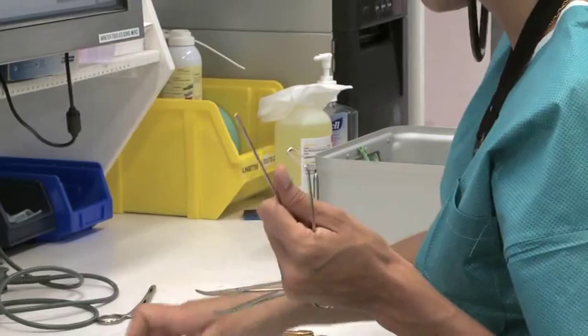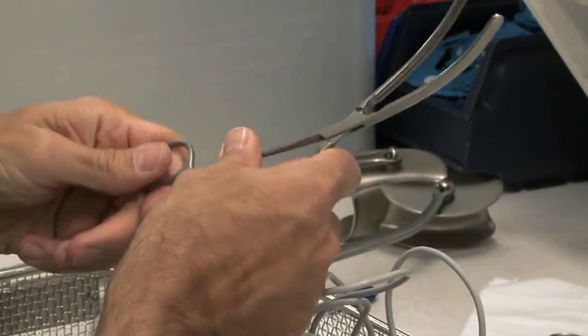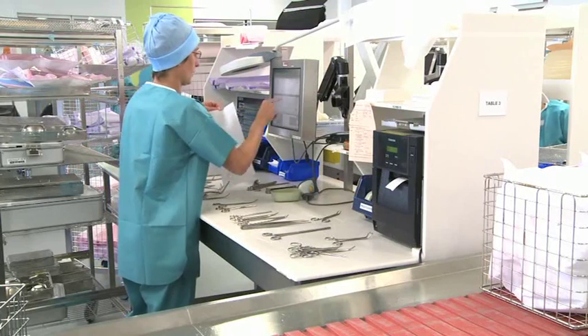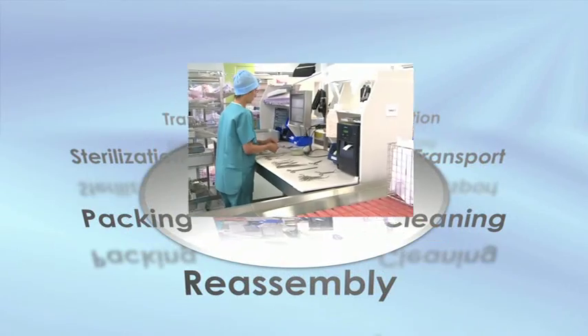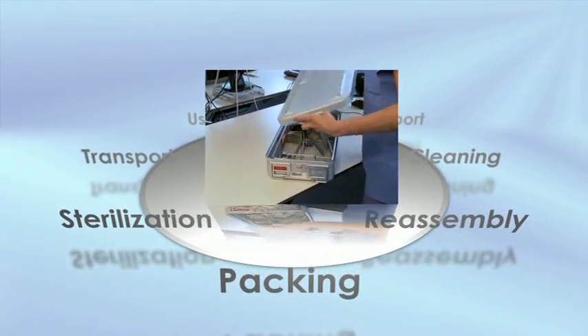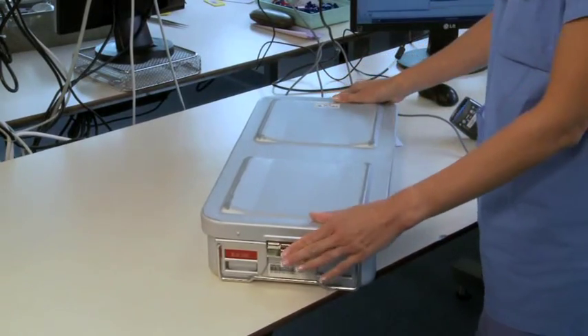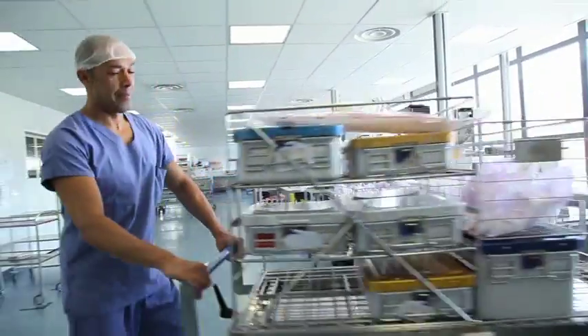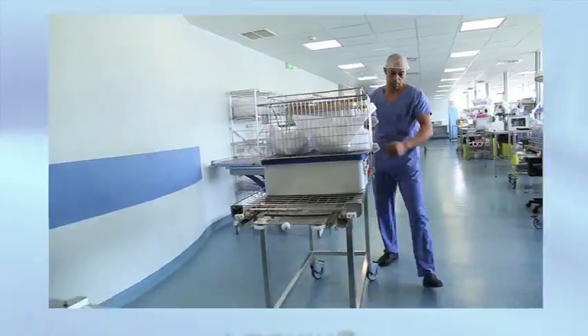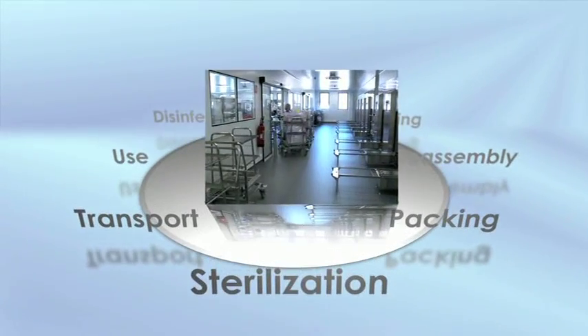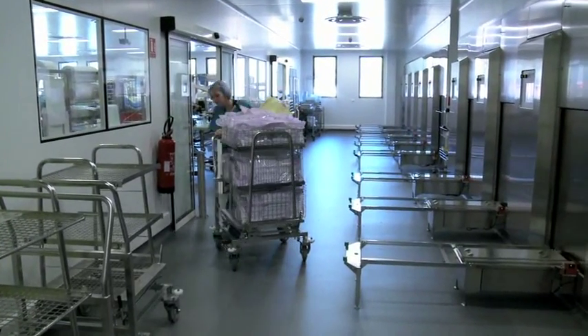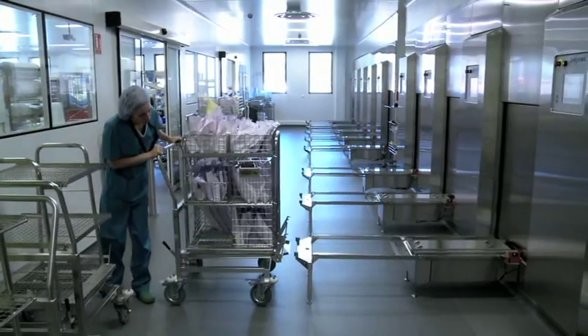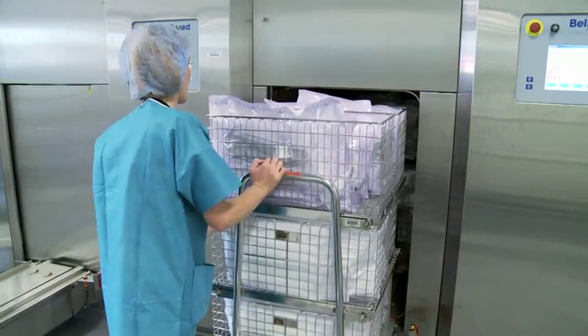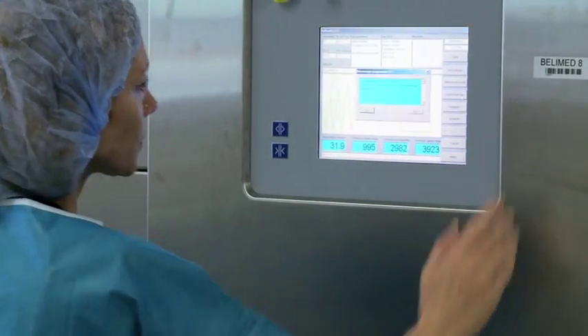Technicians check that the medical devices are clean, dry and in good condition, and they reassemble the sets assisted by a computer. The carriers and traceability labels are placed in containers that allow the sterilising agent to pass through and are loaded into the autoclaves. The sterilisation cycle takes about 1 hour and a half in the autoclaves at a temperature of 134 degrees Celsius and absolute pressure of around 3 bar during 18 minutes.